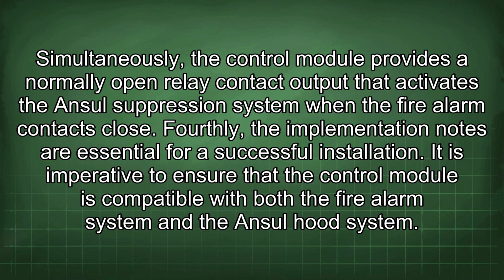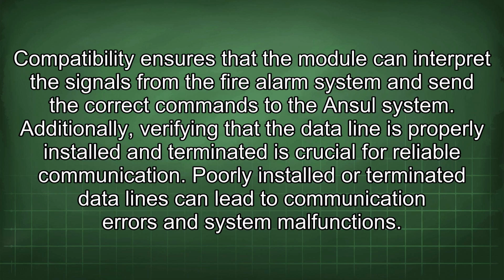It is imperative to ensure that the control module is compatible with both the fire alarm system and the Ansul hood system. Compatibility ensures that the module can interpret the signals from the fire alarm system and send the correct commands to the Ansul system. Additionally, verifying that the data line is properly installed and terminated is crucial for reliable communication. Poorly installed or terminated data lines can lead to communication errors and system malfunction.